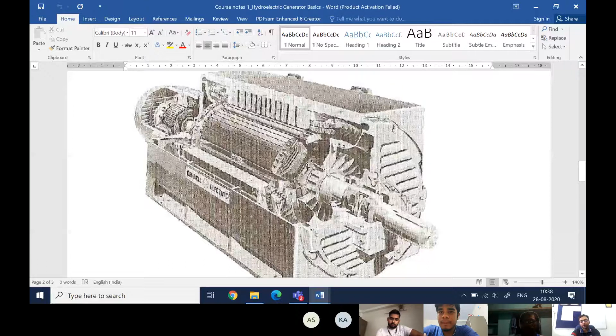Now this rotor, the rotating thing, how it is designed, determines a classification. The rotor can be of two types: one is the salient pole rotor, and the machine having it is known as a salient pole machine, and the other is the cylindrical rotor machine. Hydroelectric generators are typically salient pole machines, whereas those used in fossil fuel plants—coal-based, nuclear, or gas-based power plants—are all cylindrical rotor machines.